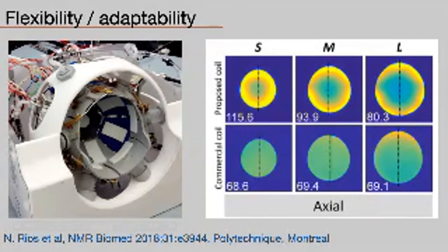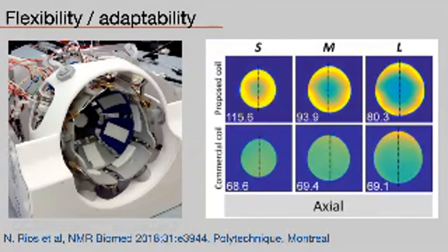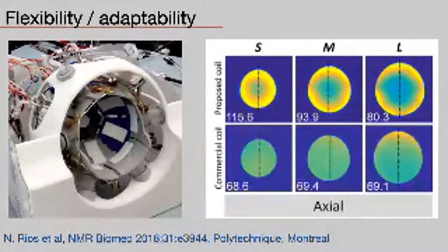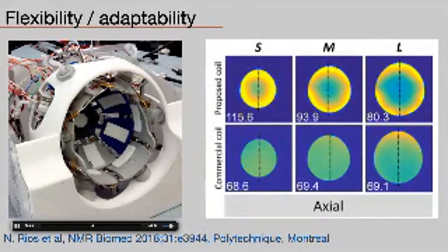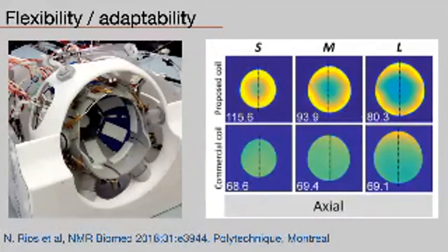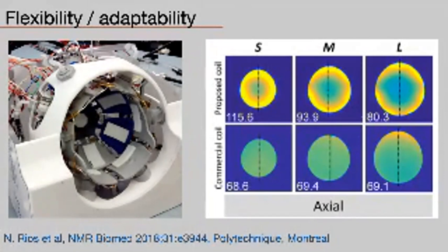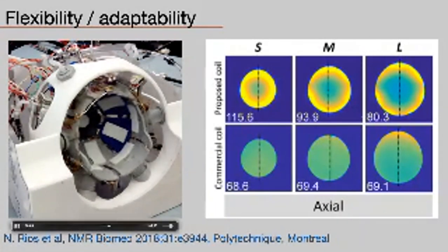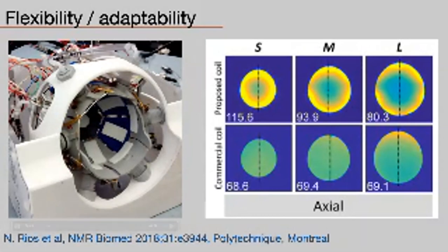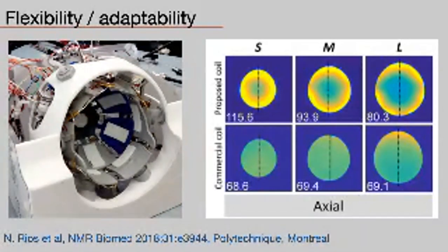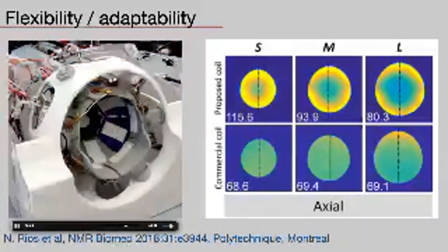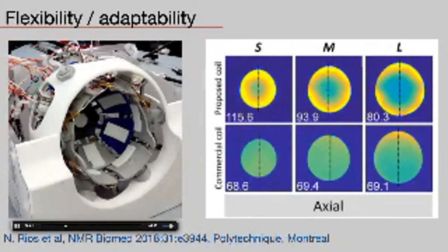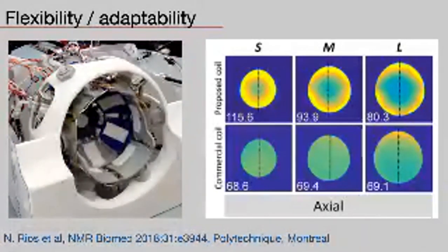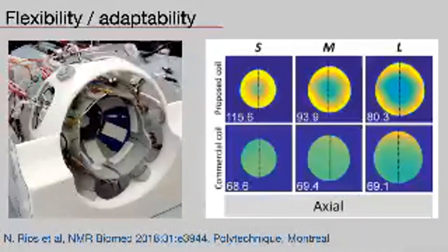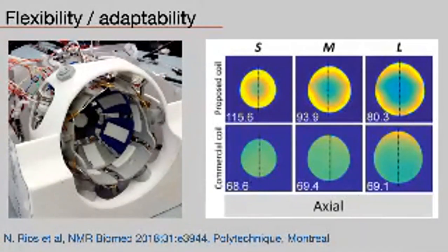To enable this, flexibility is the key, since flexible coils can naturally adapt to geometry. Here's a beautiful work from the Montreal group showing a head coil that can adapt to different patient sizes, replacing the entire array of seven coils designed in the previous slide with a single one, because it has flexibility built in. It's pneumatically moved by air pressure. You can see how the coil elements can move and produce much higher SNR for small heads while still producing very decent SNR for larger heads — way more than just a regular commercial coil.